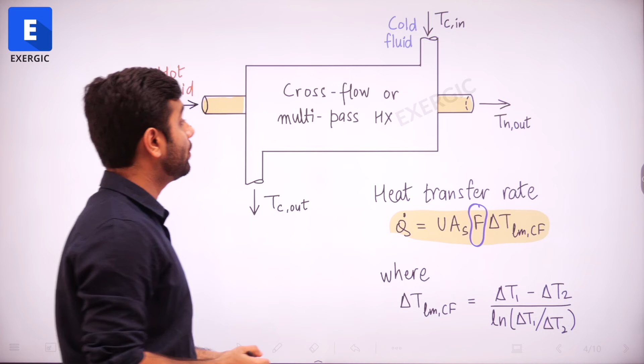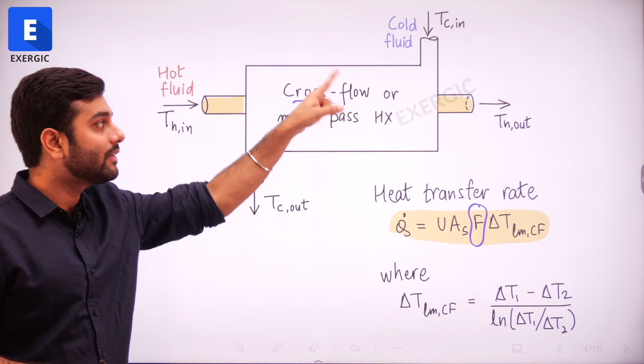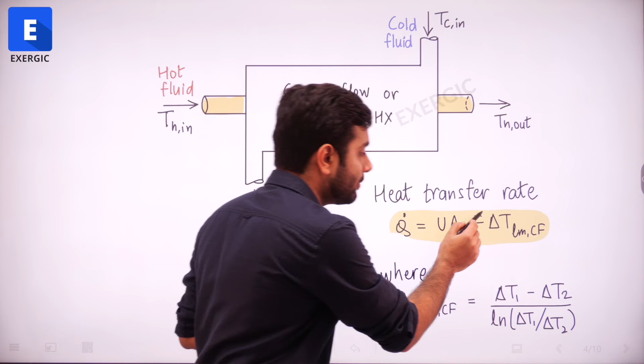Why? Because of the correction factor. I'm not saying they are counter flow, they are either cross flow or multipass, but I've represented them this way because the reference for the correction factor is counter flow only. They are not as good as counter flow; I'm showing them as counter flow, but they are slightly inferior, downgraded from it. How much downgraded is told by the correction factor.